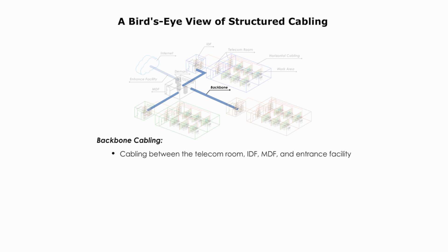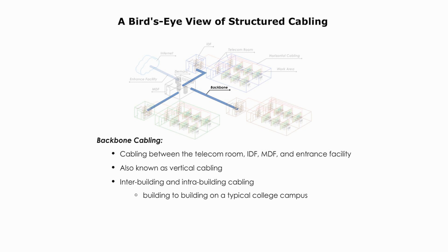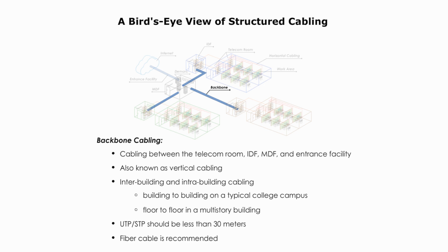Backbone cabling refers to the cabling between the telecom room, IDF, MDF, and entrance facility. It's also known as vertical cabling. It can be inter-building and intra-building cabling — for example, from building to building on a typical college campus, or from floor to floor in a multi-story building. If UTP or STP is used as backbone cabling, it should be less than 30 meters. But fiber optic cabling, multimode or single mode, is recommended nowadays.